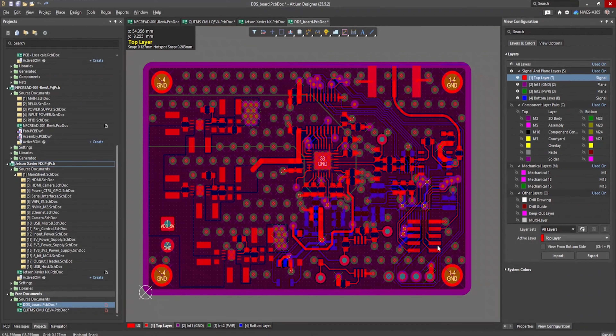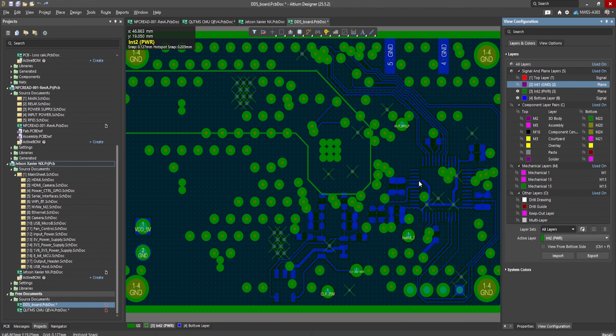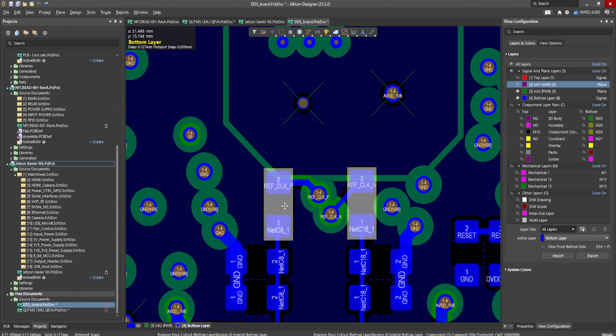Once you've received your prototypes, they will need to be tested both functionally and electrically. This could include product-specific tests or industry-specific tests that are detailed in your device specification. One of the challenges relating to the other areas we mentioned is evaluating whether your grounding strategy was actually effective. What sometimes looks perfect in a PCB layout simulation may end up failing due to incorrect ground plane connections or ground net connections, inadequate via shielding, and shielding discontinuities at connector interfaces. Designers may discover that their carefully planned grounding architecture may actually not produce the right results due to high impedances in return paths and low shielding effectiveness in certain parts of the product.